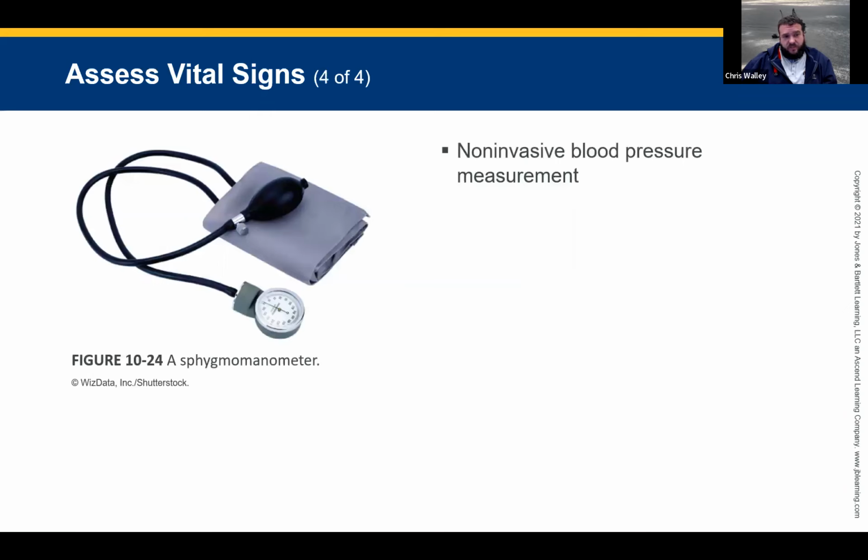So here is a picture of your non-invasive blood pressure cuff. We went over that a while ago, the different parts and pieces. So here's your gauge. Here's the little pressure release valve I was telling you about. You tighten it up to increase pressure inside the cuff, and you loosen it and see the pressure drop. They're both the same valve, and the pressure comes out of here. It lets you check the blood pressure for systolic and diastolic.